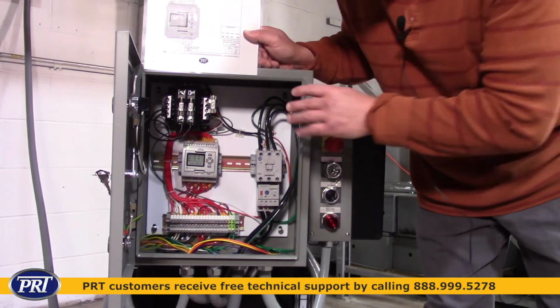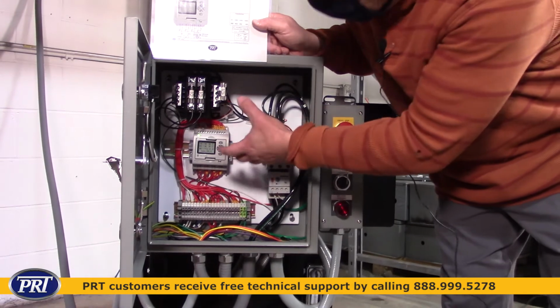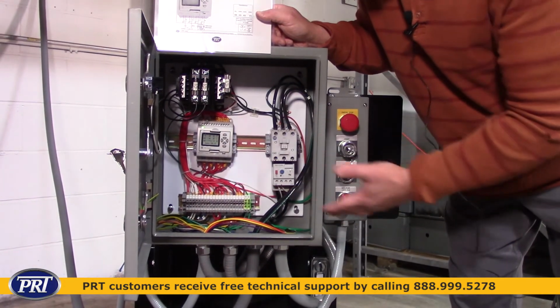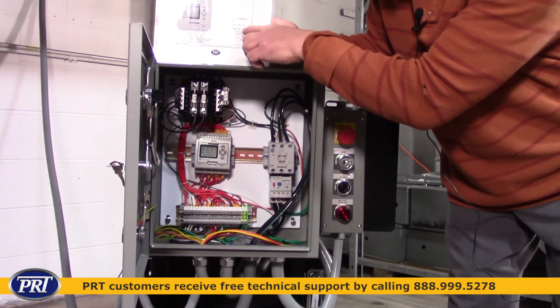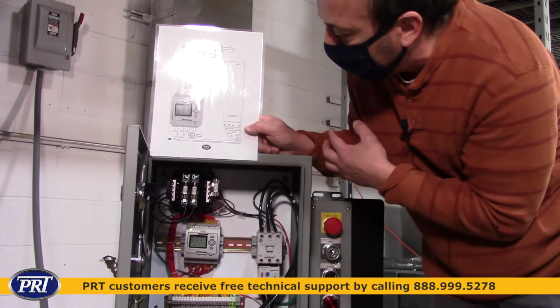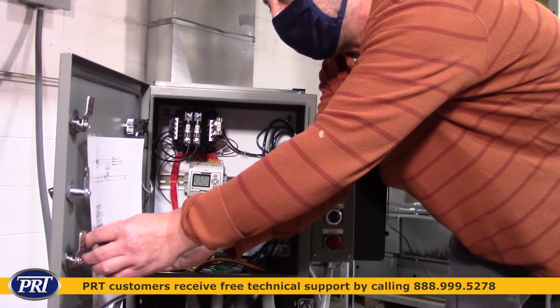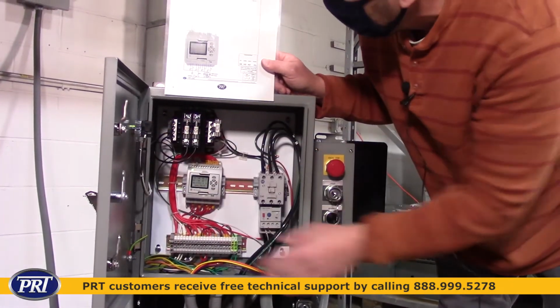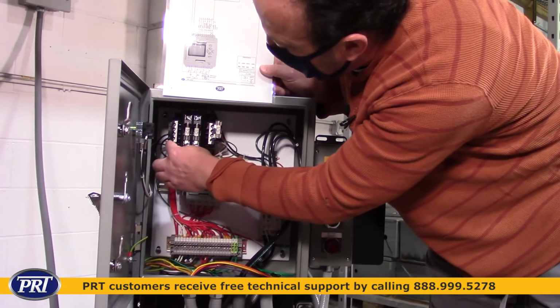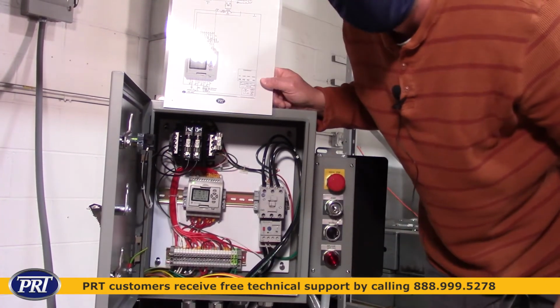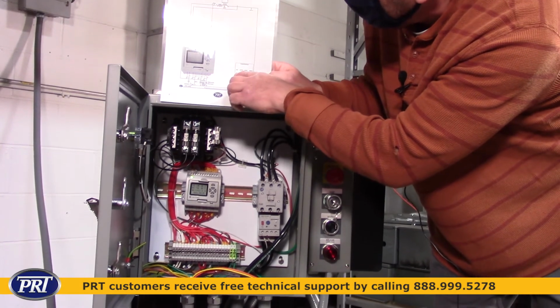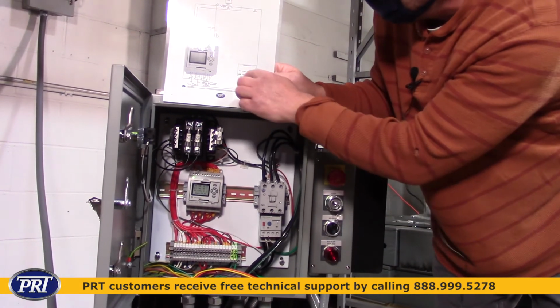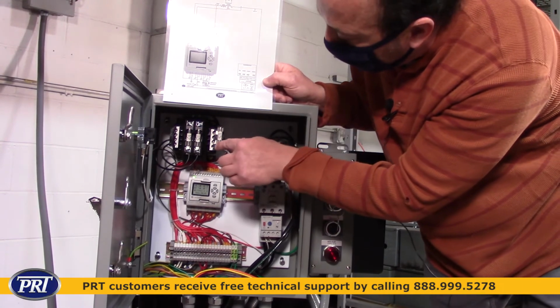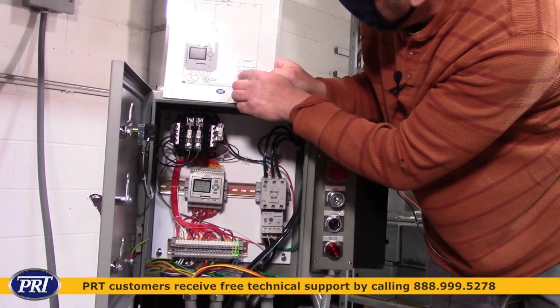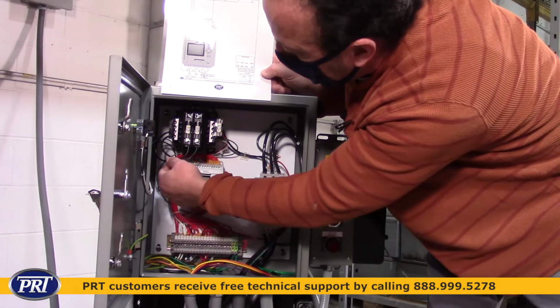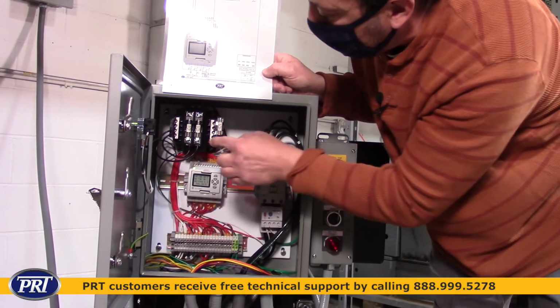To confirm if your transformer is wired correctly, they put the schematic up in there where it's really hard for a technician to see. So what we did is, on the electrical schematic, we put the transformer and how it's supposed to be laid out for different voltages, which is usually pasted right there for easy access. But in this case, you've got numbers on the side, H4, H3, H2, and H1. This right here tells me that H4 is 0, which is a wire that never moves. Now, if you want to set this transformer for 208, it would be H4 and H3. When I say that, I mean this wire here and this wire here would go to H4 and H3.